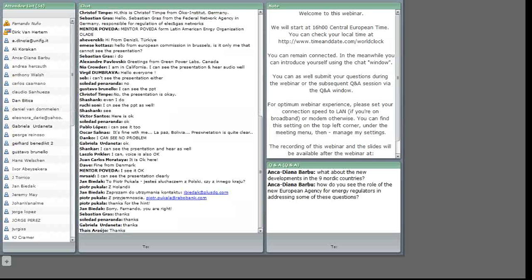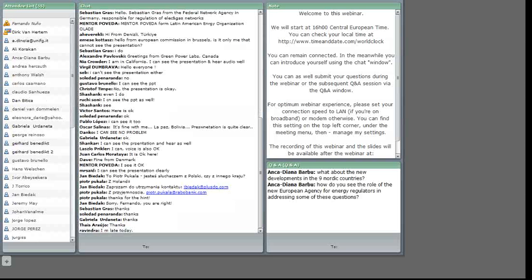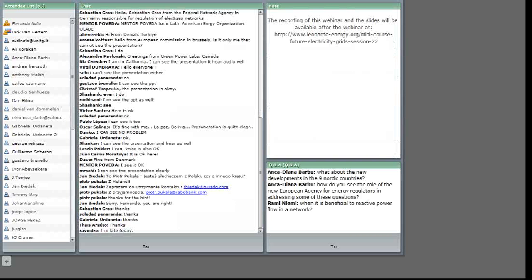I think it's not really the reactive power flow itself that you want to control in the system - the reactive power flow is in a network. You want to have reactive power available only at the places you need it, and that means you have to provide it as voltage support. So you don't really sell reactive power; the only thing is you need it for good system operation. So in cases where you have local reactive power problems, you want this solution. Then you typically use a STATCOM or an SVC device to boost up the voltage or to compensate for flicker in the system caused by, for instance, a wind farm.